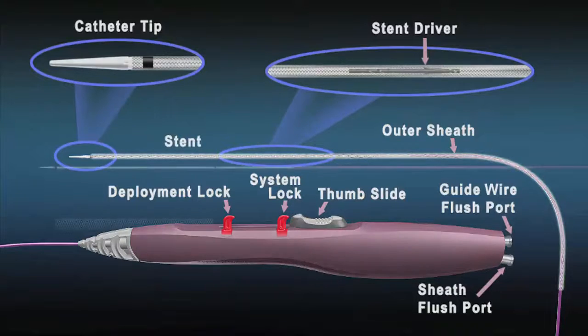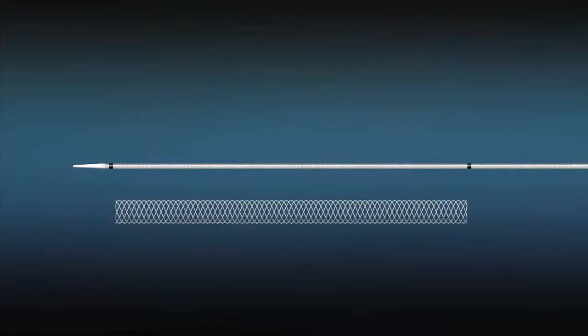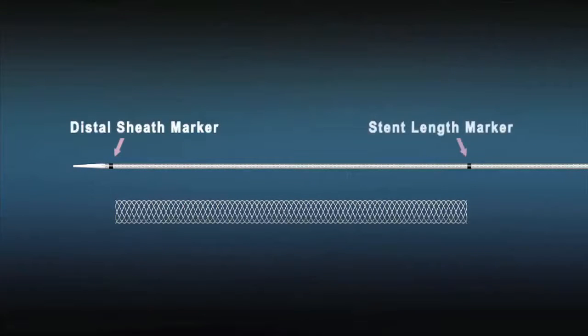Note that the Supera implant is constrained at approximately 3 times its nominal length within the delivery catheter. Proper deployment is critical to restoring the Supera implant to its nominal state, maximizing its radial strength and flexibility. The distance between the distal sheath marker and the stent length marker indicates the nominal length of the implant. The markers have significance only prior to implant deployment, serving to identify the distal and proximal landing zones.